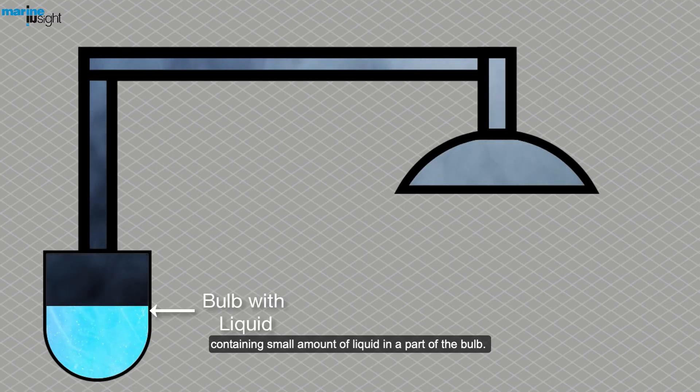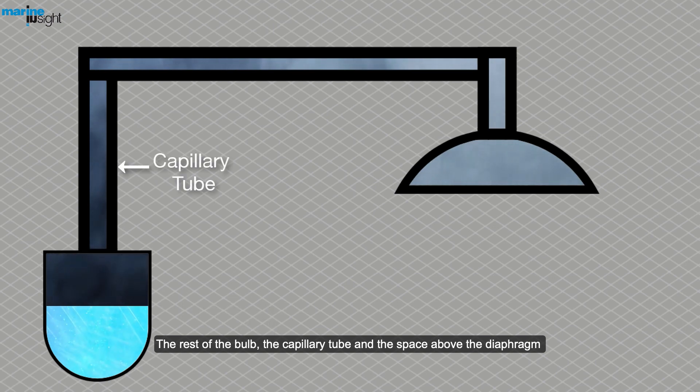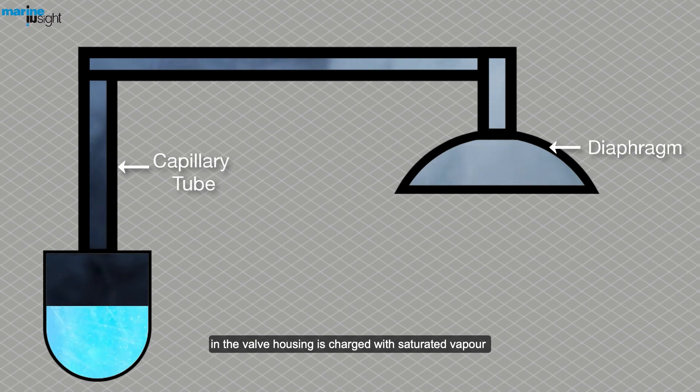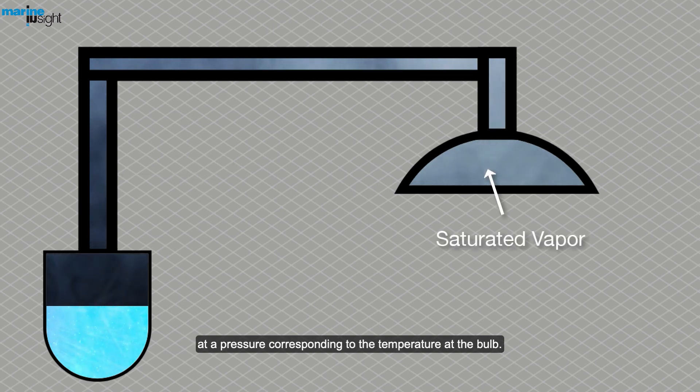The rest of the bulb, the capillary tube and the space above the diaphragm in the valve housing is charged with saturated vapor at a pressure corresponding to the temperature at the bulb.